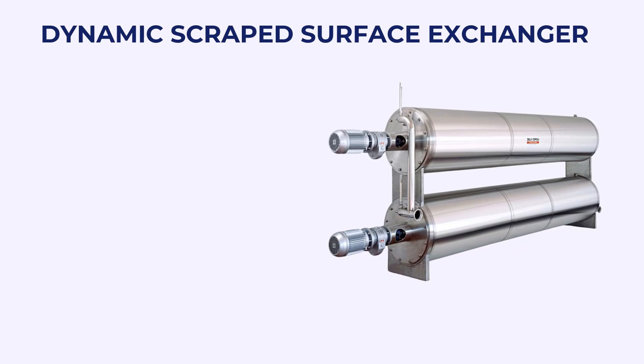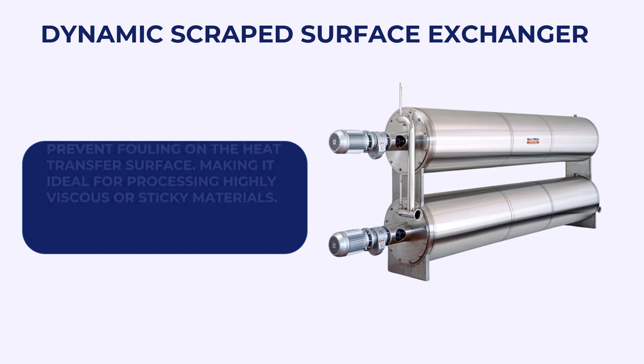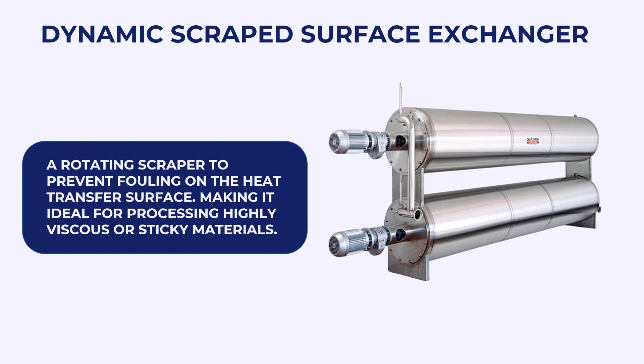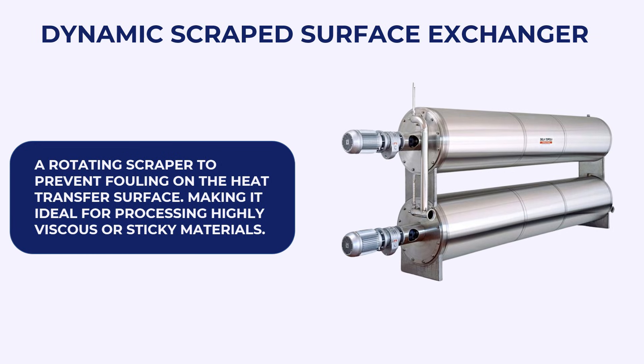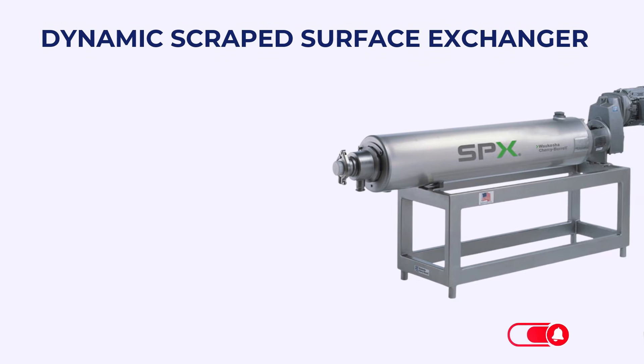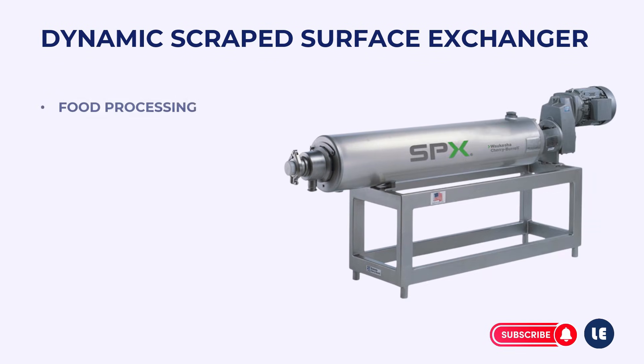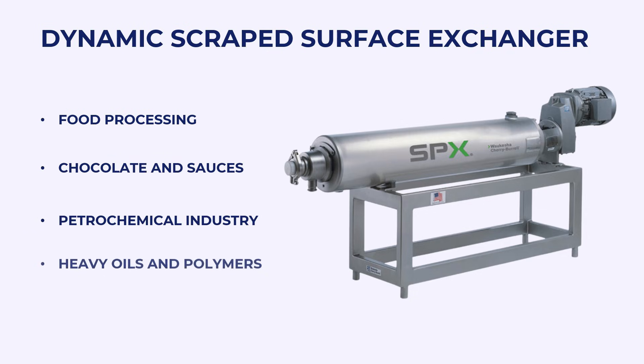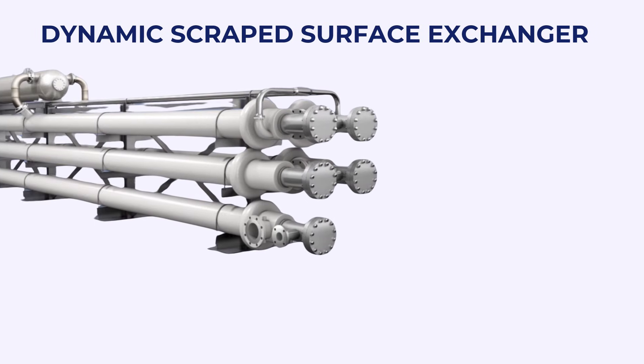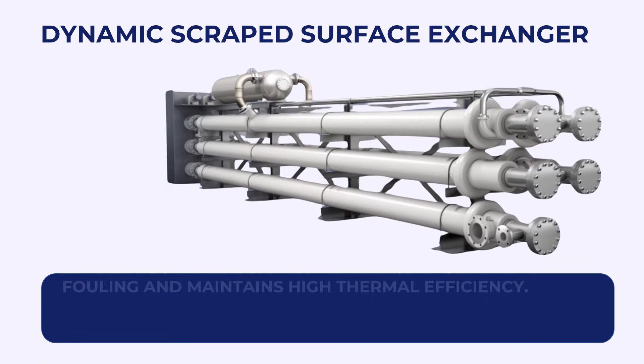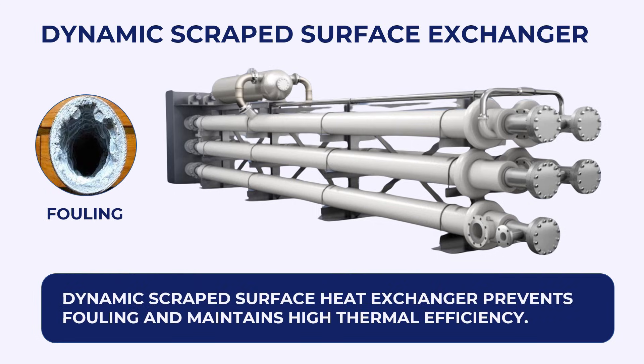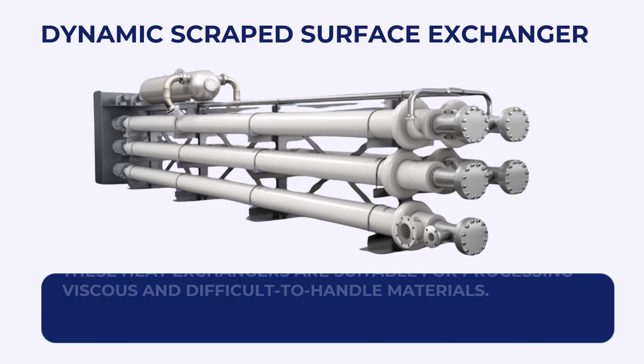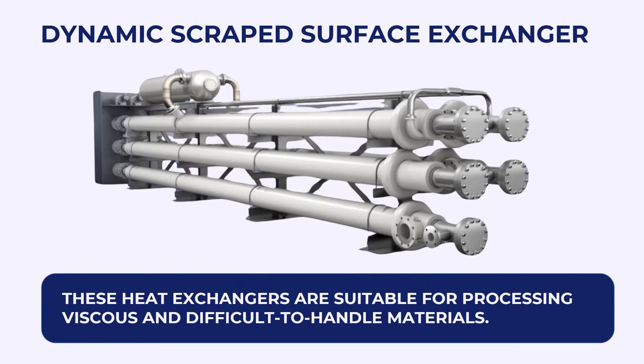Dynamic Scraped Surface Heat Exchanger. A dynamic scraped surface heat exchanger includes a rotating scraper to prevent fouling on the heat transfer surface, making it ideal for processing highly viscous or sticky materials. It is used in food processing for chocolate and sauces, and in the petrochemical industry for handling heavy oils and polymers. It prevents fouling and maintains high thermal efficiency, and is suitable for processing viscous and difficult-to-handle materials.